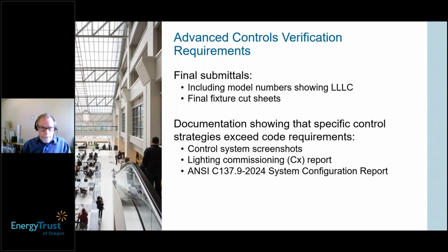It could be, if people are familiar with it, the ANSI C137.9 format report that just got released near the end of last year. That's an advanced controls standardized reporting format that gives details about your time-to-off, occupancy settings, and all those things. That would be a wonderful help in showing what you're doing with your control system and allowing us to verify that the system is actually doing beyond-code strategies.